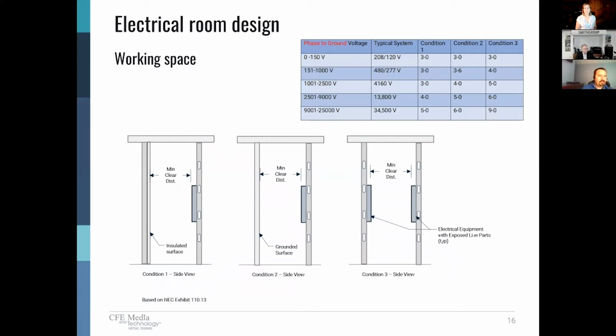So as Brian mentioned, the working clearance depth is dependent upon a couple of different things. One being the nominal system voltage, but also a couple of different conditions. It's really about where the panel, the switchboard, the switchgear is installed and what is directly across from it. So condition one, if you take a look at the side view on the left side of the screen, is depicting an insulated surface directly across from the panel. An insulated surface would typically be drywall or sheetrock type installation. Condition two being a panel board or switchboard or switchgear directly across from a grounded surface, such as masonry, concrete, block or tile.